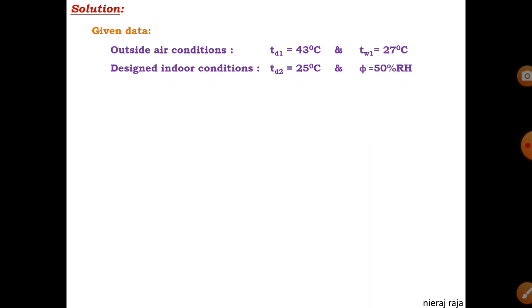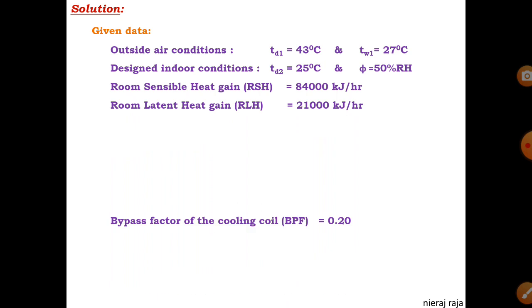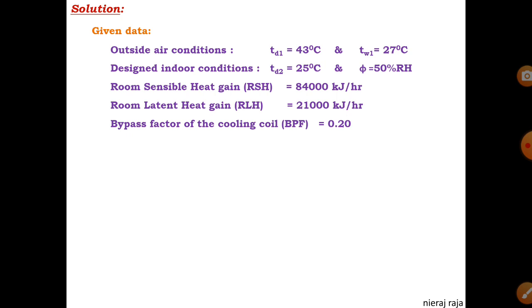Let us sort out the given data. Outdoor air condition: TD1 = 43°C, TW1 = 27°C. Design indoor air condition: TD2 = 25°C, 50% RH. Room sensible heat gain (RSH) = 84,000 kJ/hr. Room latent heat gain (RLH) = 21,000 kJ/hr. Bypass factor (BPF) = 0.2. Total supplied air: 80% recirculated air and 20% fresh air.